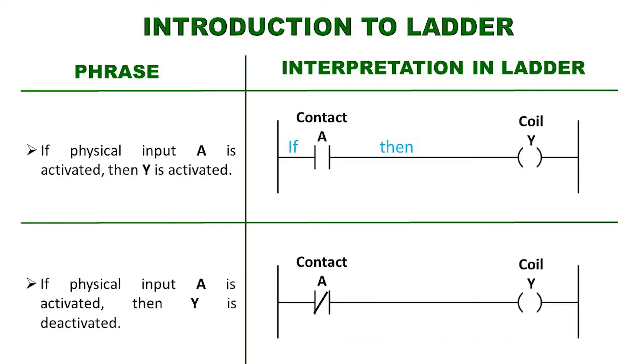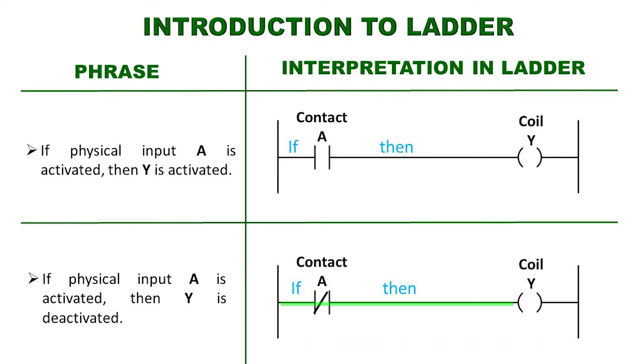Another sentence might say: if physical input A turns on, then Y turns off. This could be represented on the ladder diagram with a normally closed contact A and a Y coil, and would be interpreted as follows: if contact A receives a logical one, then this contact changes state — that is, it opens — and thus can deactivate coil Y, since it was initially activated because contact A is normally closed. To reactivate the Y coil, it would only be enough to deactivate the physical input, thus contact A would return to its default state, which is normally closed.